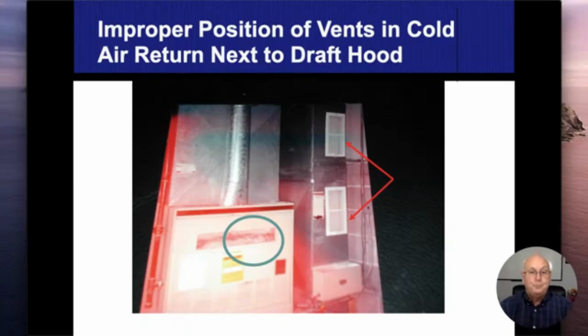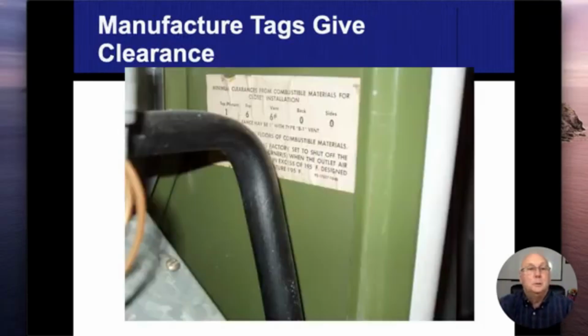But here, in this situation, we're in a room where we were depressurizing that room. Now, if you look at the green circle, you can see all the corrosion and rust, and that negative pressure in there was causing this furnace to backdraft. And not only are we backdrafting, but now we're pulling all that carbon monoxide right into our circulation air, and we're just putting it into the house. This house did have a carbon monoxide alarm in it. It was going off. And this is what we determined to be the cause of that: the furnace was backdrafting and pulling the carbon monoxide into the circulation air until eventually it set off the carbon monoxide alarms.